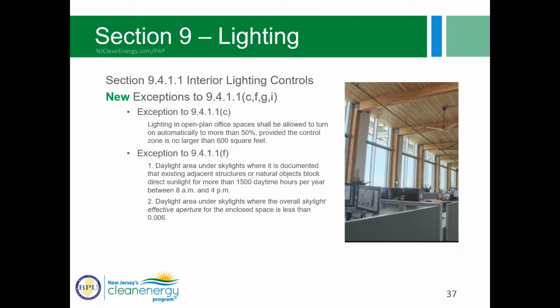All right, so with the interior lighting controls, there are four new exceptions, and these are pretty specific and not necessarily applicable to every single project. So going through these, it's more just for awareness, something to keep in mind as you're developing your projects. So the exception for item C applies to restricted to partial automatic on controls, where it's limited to 50% unless it's an open office plan and is less than 600 square feet.